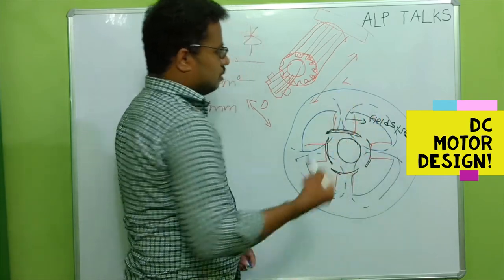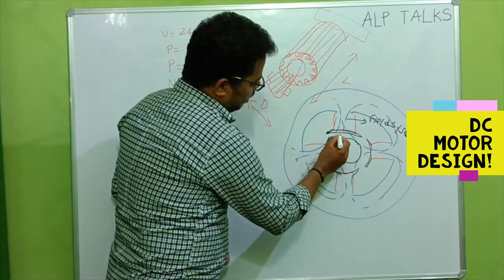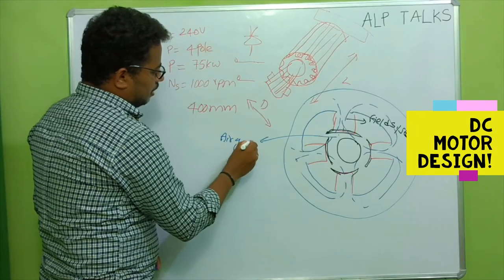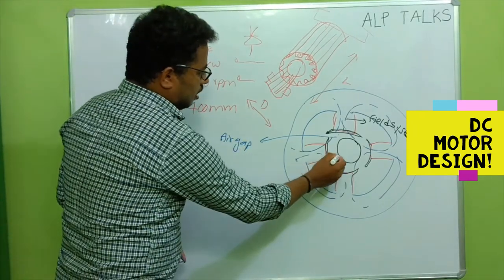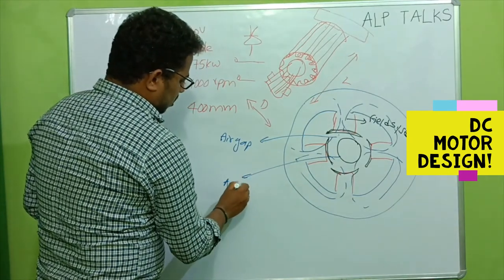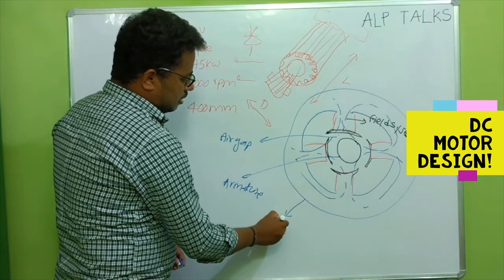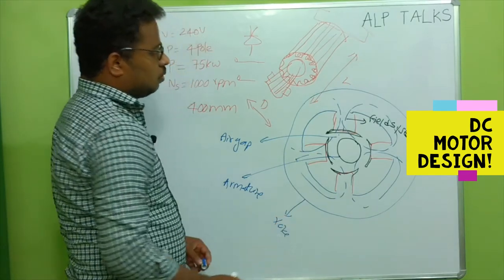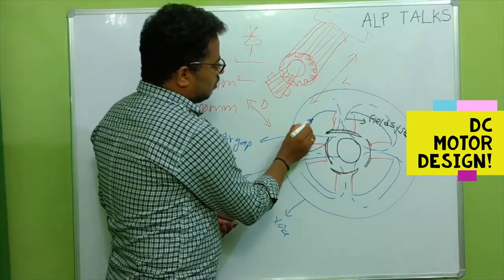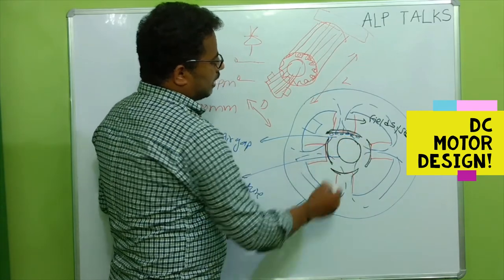Here whatever space is there, we are providing some empty space between - this is the armature and this is the air gap, and this is the yoke arrangement. Sometimes for higher ratings we may have some interpoles here and some compensating windings to take care of armature reaction and for better commutation.